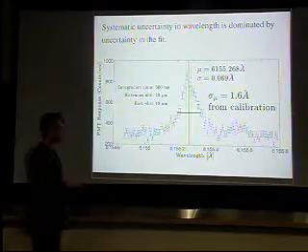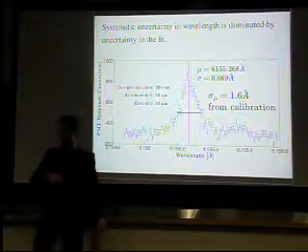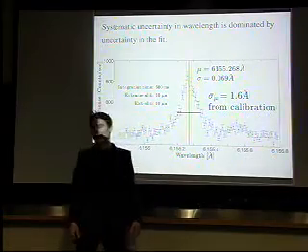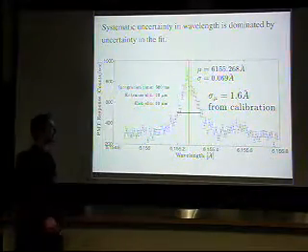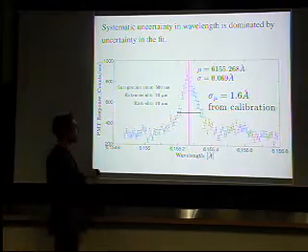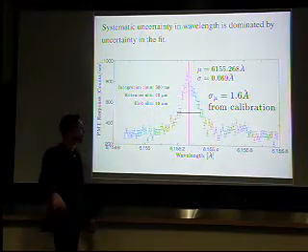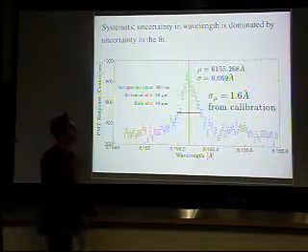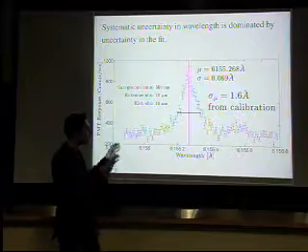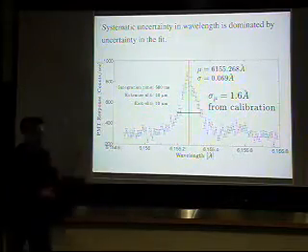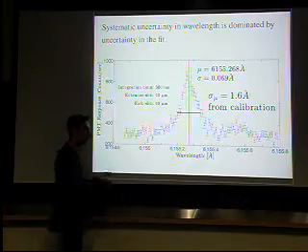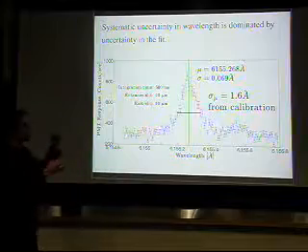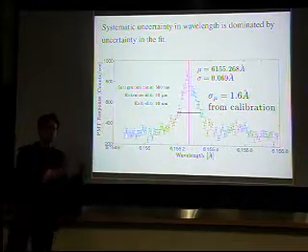We have our wavelength, which is calibrated. The way we calibrate is we take a look at a mercury spectrum, and we know the mercury emission lines. Smarter people than I have measured these things, so I trust them. The calibration data points are from NIST. This is a typical run for 10 micron entrance and exit slits. Each point is taken over 500 milliseconds. We're just changing the angle of the grating and looking at different wavelengths. And what I really want to talk about here is how we determine the center of the peaks that we're looking at.